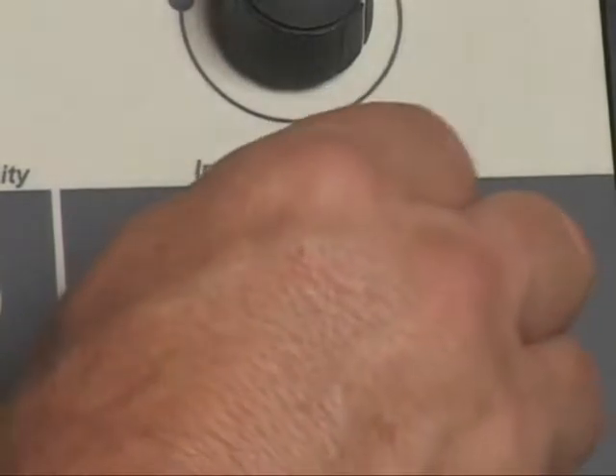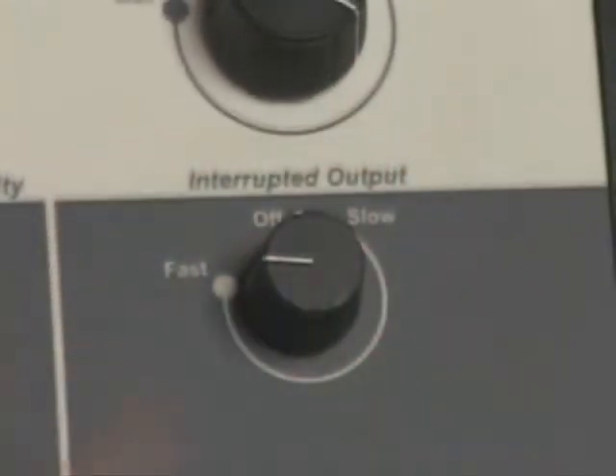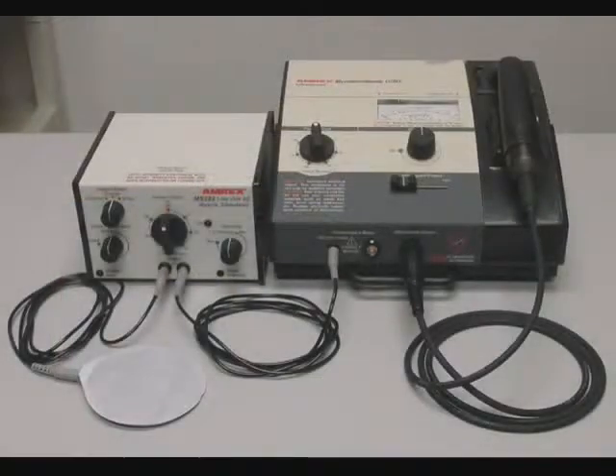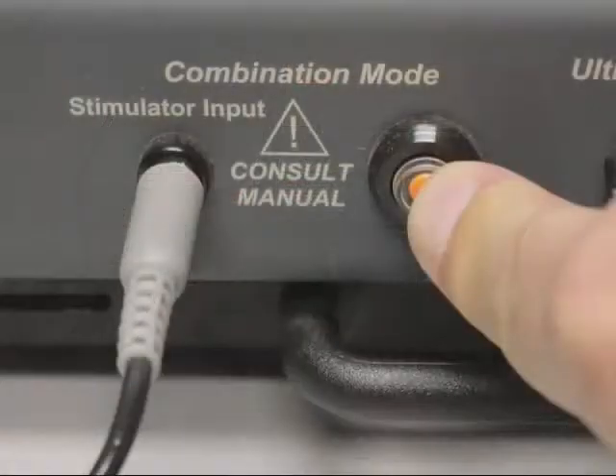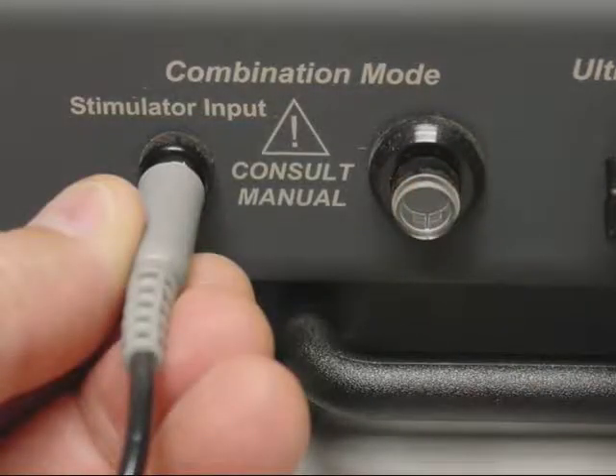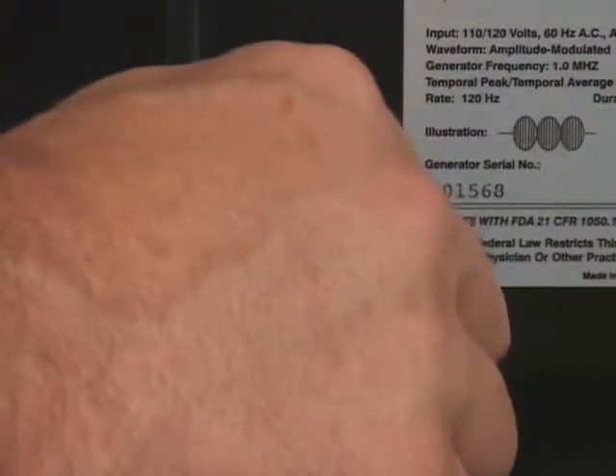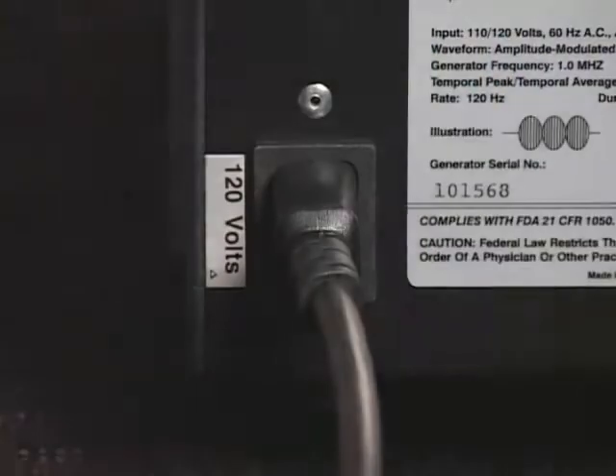patient. Interrupted ultrasound output can be achieved by rotating the interrupted output control clockwise, enabling the audible click, and setting the interrupted output control to the desired output interval. Combination therapy is ultrasound and a stimulator modality applied through the ultrasound transducer simultaneously. Depressing the U50 combination mode switch to the on position and properly connecting an external stimulator to the U50 can enable combination therapy.